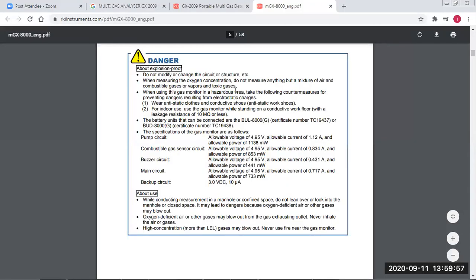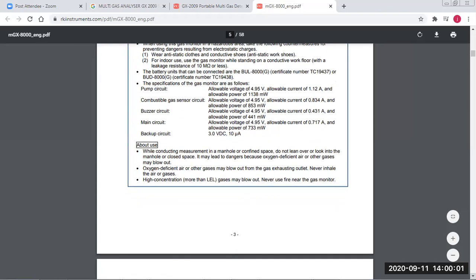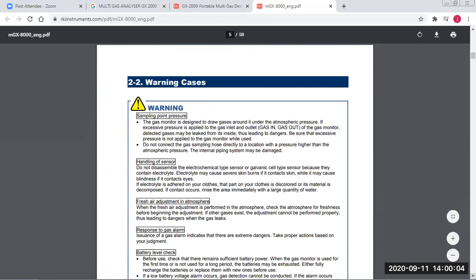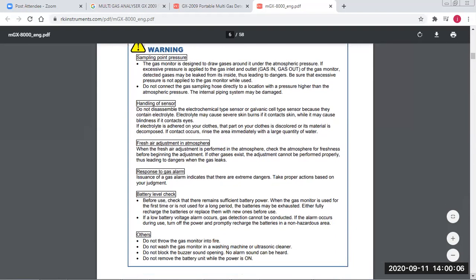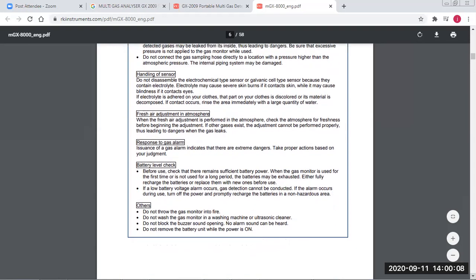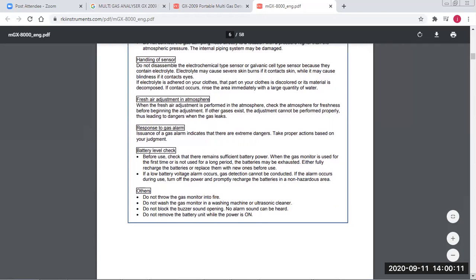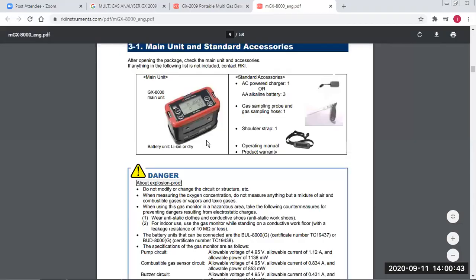Then in your instruction manual, some safety measures are mentioned. Do not change the circuit, and the battery should be maintained. Sampling point pressure should not exceed the limit. Handle very carefully, and do not remove the sensors unless you are changing them, or the galvanic type sensor, because they contain electrolyte. So this is your multi-gas detector, which is measuring your oxygen, hydrocarbon, carbon monoxide, and H2S.